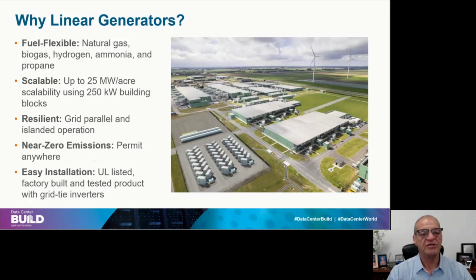So why the linear generator? This is a real site, a 25 megawatt site. It's fuel flexible, and unlike the solid state fuel cell which really needs hydrogen, requiring a lot of processing of the natural gas, linear generators are very fuel flexible. I could pump in anything, natural gas, biogas, hydrogen, ammonia, propane, and they will work. They're highly resilient, near zero emissions so I could permit them anywhere, and they're a very easy installation.